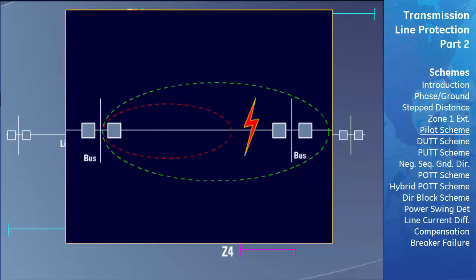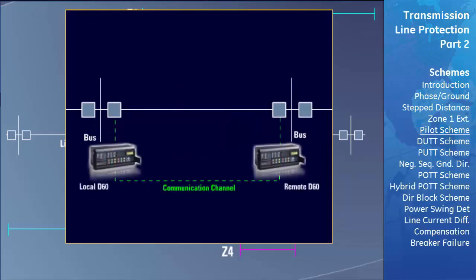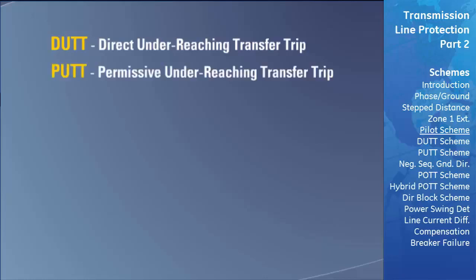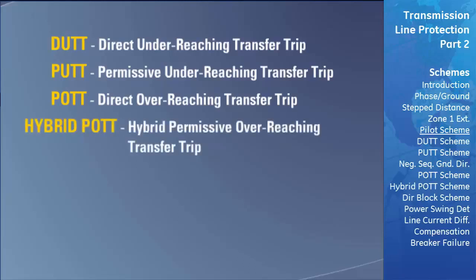Pilot schemes speed up fault clearing inside Zone 2 of the local relay by communicating with the relay at the remote end to determine if the fault is actually on the transmission line. All pilot-aided schemes require a communication channel between the two relays. The most common pilot-aided schemes are the DUTT scheme (Direct Under-Reaching Transfer Trip), the PUTT scheme (Permissive Under-Reaching Transfer Trip), the POTT scheme (Permissive Over-Reaching Transfer Trip), the hybrid POTT scheme (Hybrid Permissive Overreaching Transfer Trip), and the directional blocking scheme.